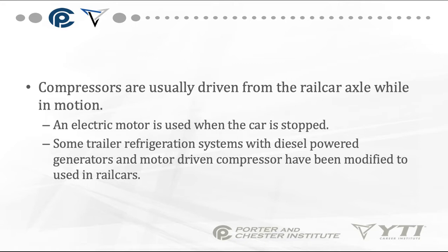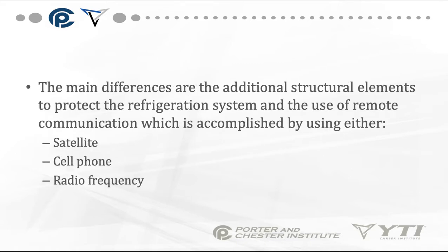Some trailer refrigeration systems with diesel-powered generators and motor-driven compressors have been modified to be used in rail cars. The main differences are the additional structural elements to protect the refrigeration systems and the use of remote communication, accomplished by either satellite, cell phone, or radio frequency. Trains are long, so you have to be able to monitor and control the temperatures at different components remotely.